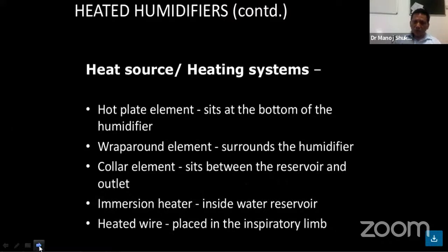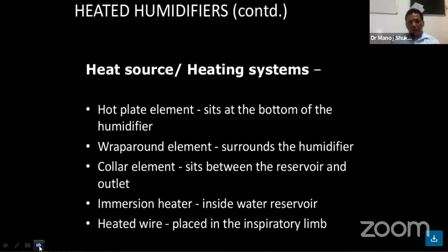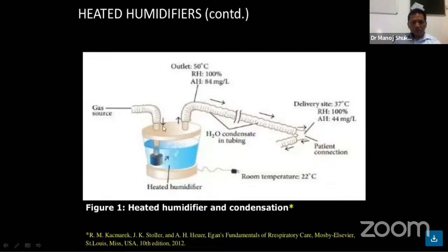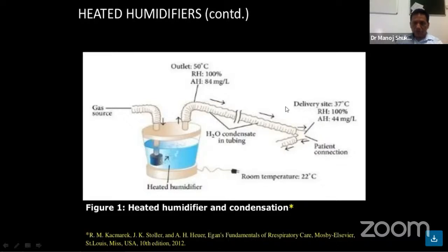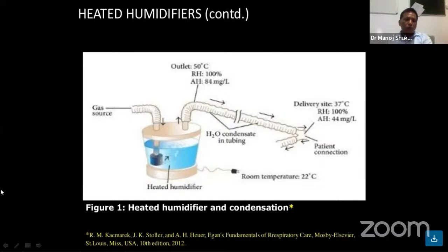In the heated humidifier, a hot plate element sits at the bottom, and a wraparound element is wrapped around the humidifier. A collar element sits between the reservoir and the outlet. Heat is applied inside the water to bring it to the boil. The gas from the source is delivered through the heated humidifier, and at the patient's end the outlet temperature is around 50 degrees with 100% relative humidity. As it passes through the tube it condenses, and at the time of delivery to the patient, the temperature reduces to around 37 degrees with 100% relative humidity — this is the ideal delivery of humidification to the patient.